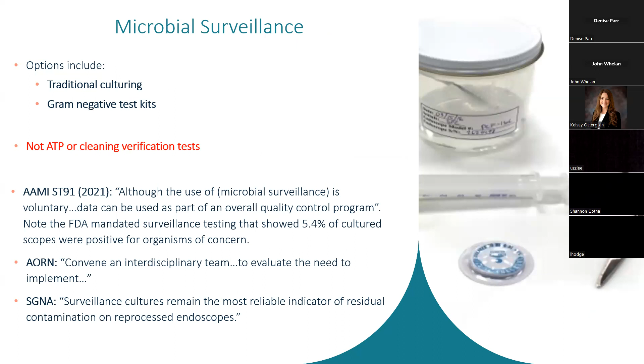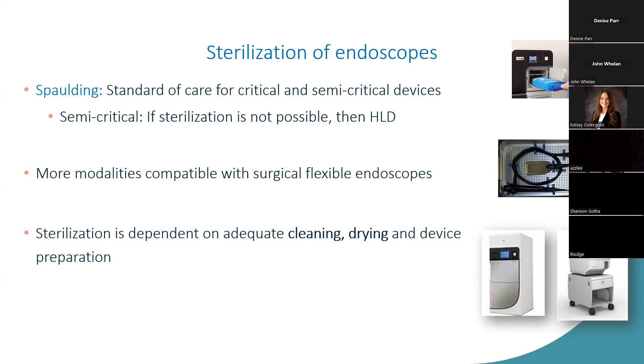For semi-critical devices, it wasn't intended that HLD was the one and only option, but rather if sterilization wasn't possible, then high-level disinfection. As we know, flexible endoscopes are heat sensitive, so they're not compatible with steam and other sterilization modalities. ETO sterilization, while it's compatible, is not available to many facilities, but there are sterilization options available though, especially for scopes used in surgical settings.